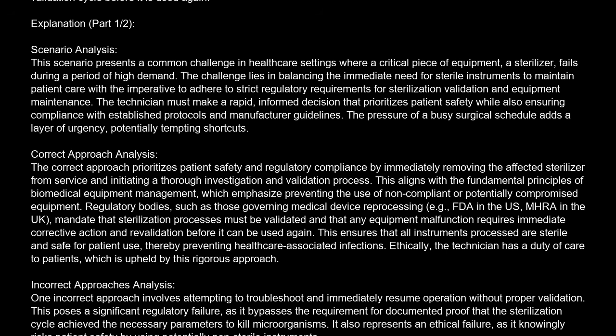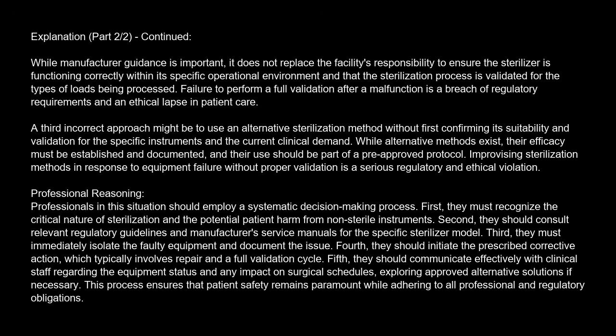Incorrect approaches analysis. One incorrect approach involves attempting to troubleshoot and immediately resume operation without proper validation. This poses a significant regulatory failure, as it bypasses the requirement for documented proof that the sterilization cycle achieved the necessary parameters to kill microorganisms. It also represents an ethical failure, as it knowingly risks patient safety by using potentially non-sterile instruments. Another incorrect approach is to rely solely on the manufacturer's basic troubleshooting without engaging in a full validation cycle. While manufacturer guidance is important, it does not replace the facility's responsibility to ensure the sterilizer is functioning correctly within its specific operational environment, and that the sterilization process is validated for the types of loads being processed.